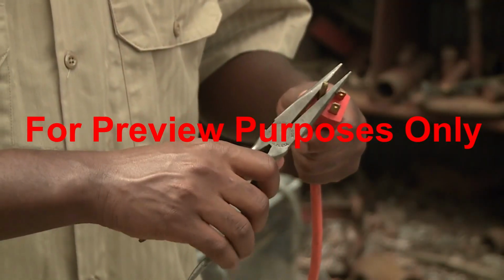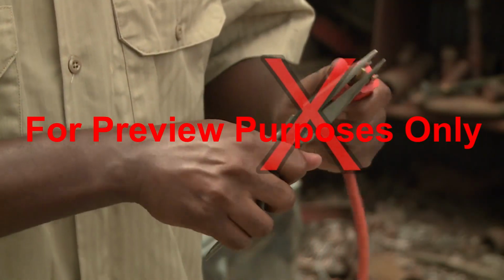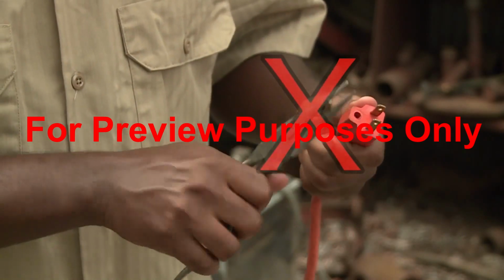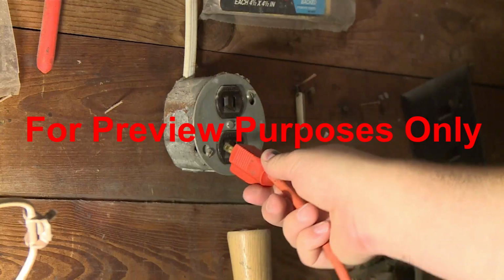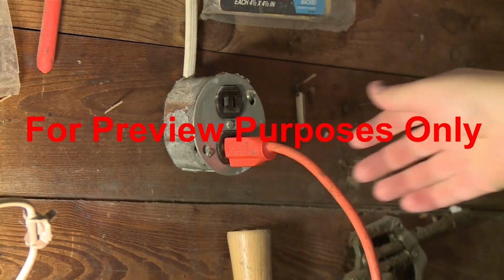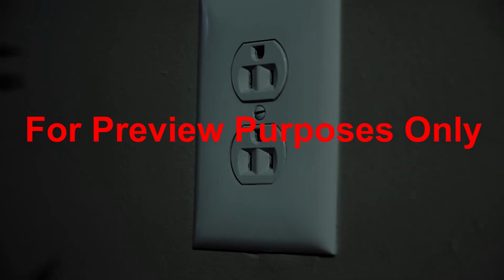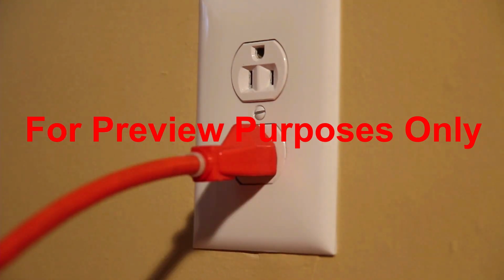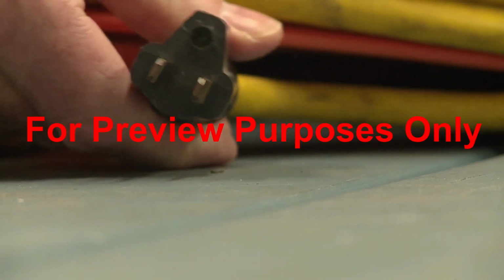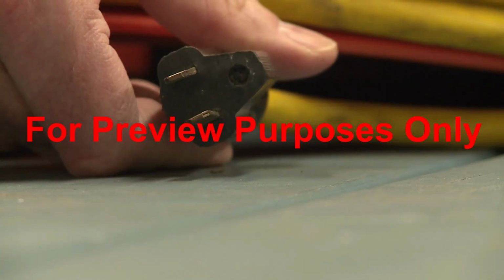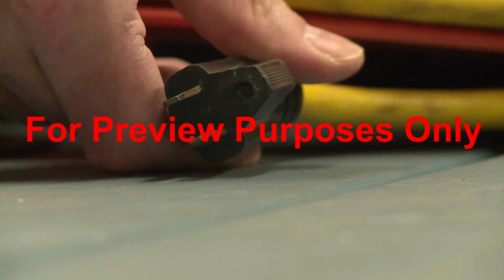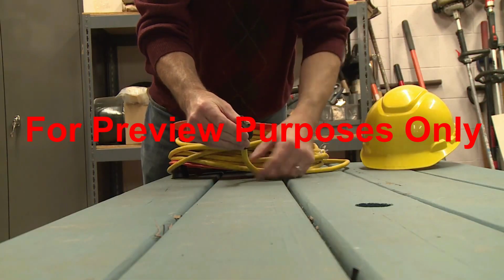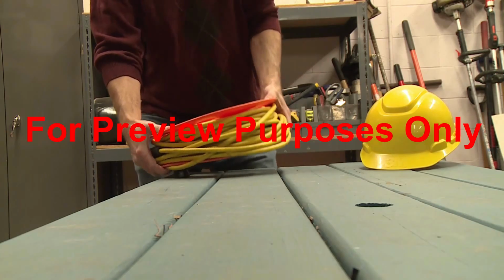And never remove the ground prong from a plug or use an adapter as a quick and easy way to connect a 3-prong plug to an ungrounded 2-prong outlet. Proper grounding helps protect you from being injured or killed by stray electricity. If you find a grounded plug with the 3rd prong removed or an adapter being used without the ground wire connected to the receptacle, take that equipment out of service at once.